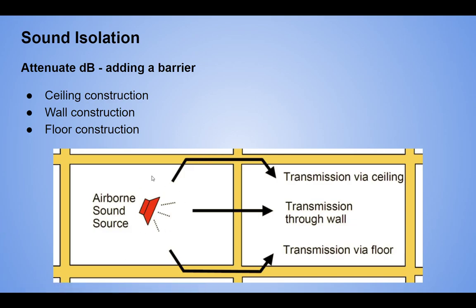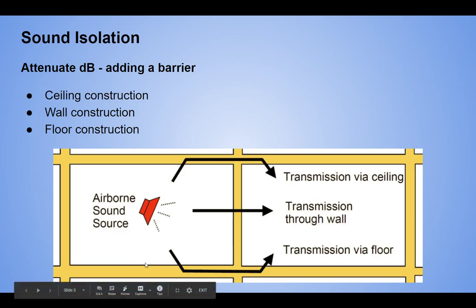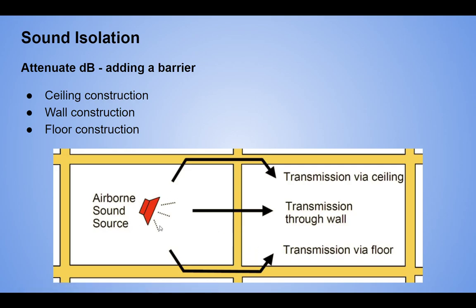We've got airborne sound here. The source is our air handling unit, some sort of mechanical equipment, and we have transmission through the wall — up and above, and down below. This is usually the flanking path detail when your wall does not go all the way to the structure above and is not resiliently sealed. If your equipment is sitting directly on the slab, you can have vibration flanking on that path.